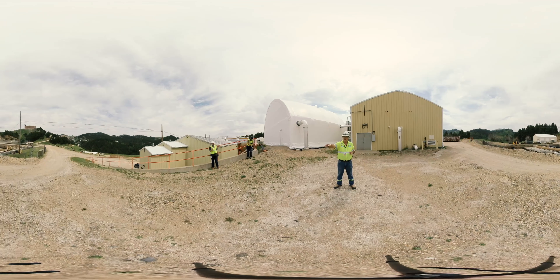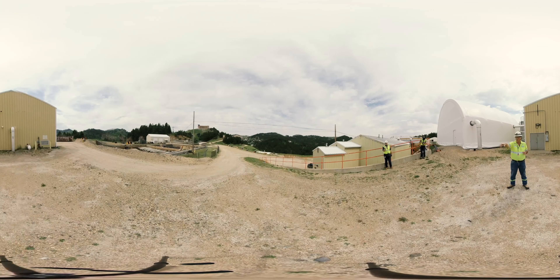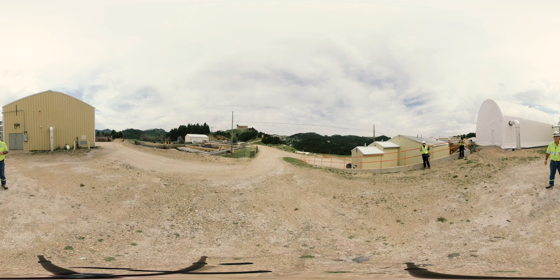I'd like you to look down to the bottom of the hill here. You'll see those concrete pillars or concrete stands there. Those concrete stands are actually an underground reservoir — it holds about 20,000 gallons of water. Any water that seeps from around the plant, anything that's spilled on the floor, anything in any of the basins you see around here, is collected down into those tanks. That water is later reprocessed back up into the beginning of the plant and re-cleaned, so no water leaves this plant without being treated.